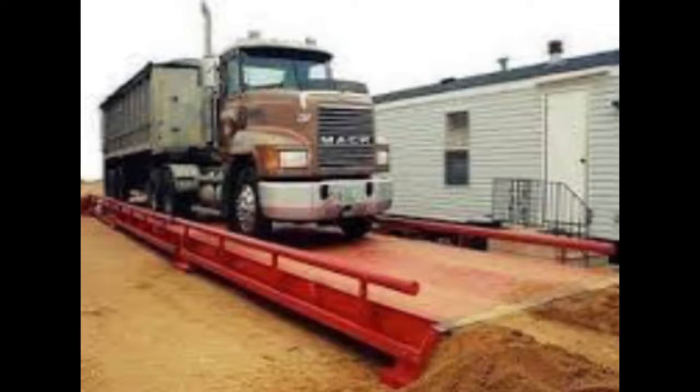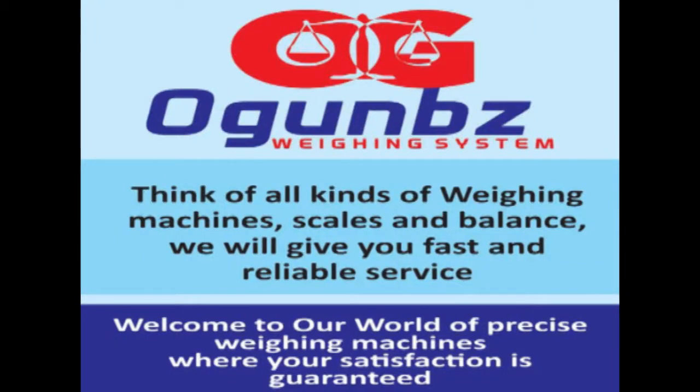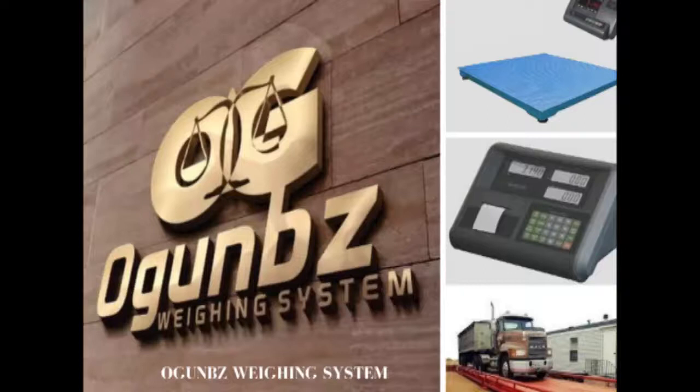But if what you want is just a temporary or stopgap measure, maybe the surface type is what you need. Maybe you do not do this weighing on a regular basis and you just need something in the interim. So what you're going to need is this other one, which is the surface weighbridge. Both can serve you depending on what you need. But in the long run, the pit mounted weighbridge is essential and very key, because it could stay for a longer period of time. So this is exactly what you need.